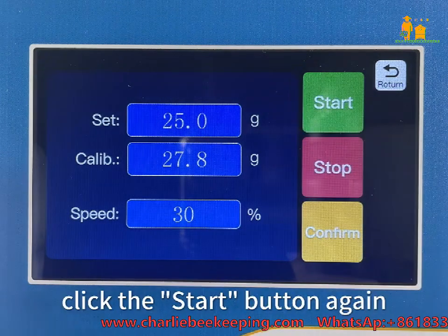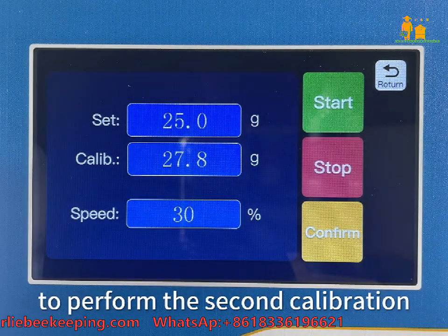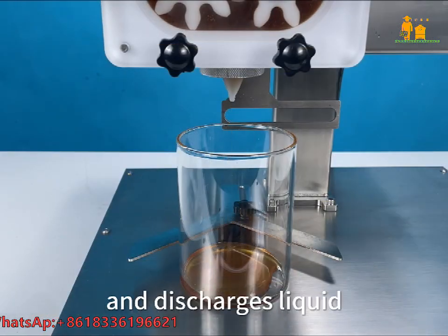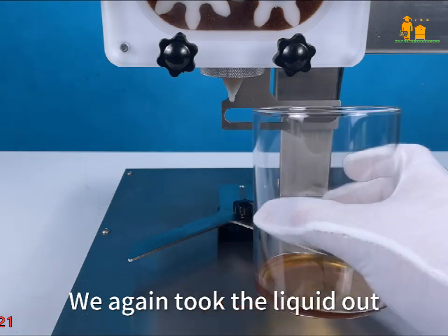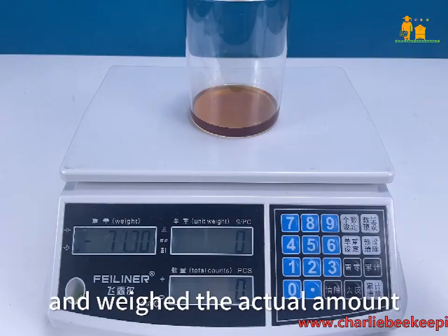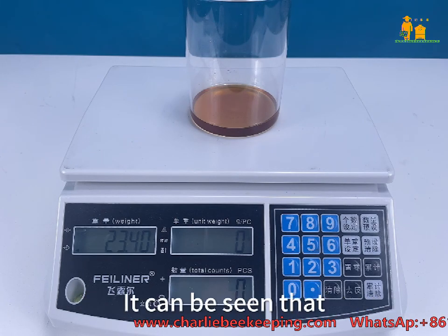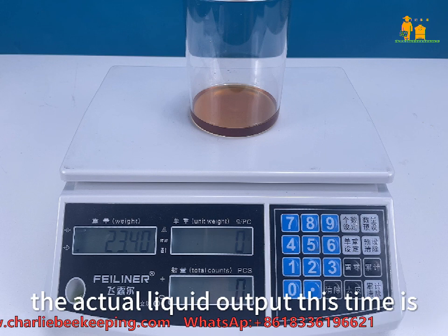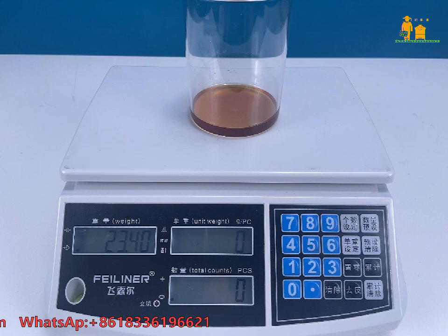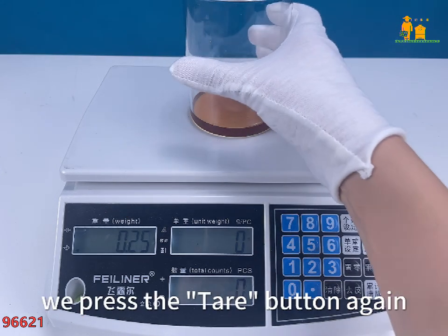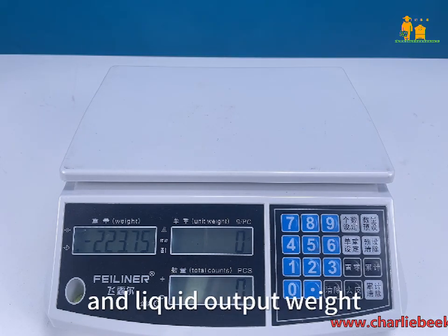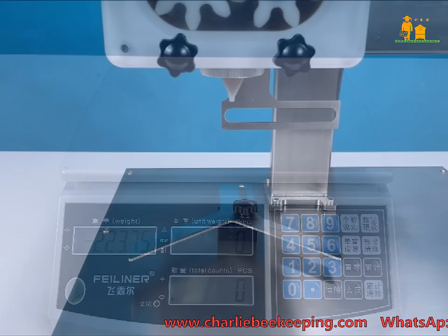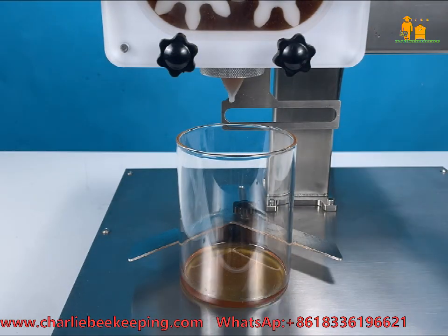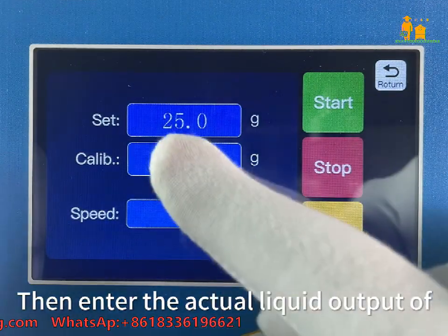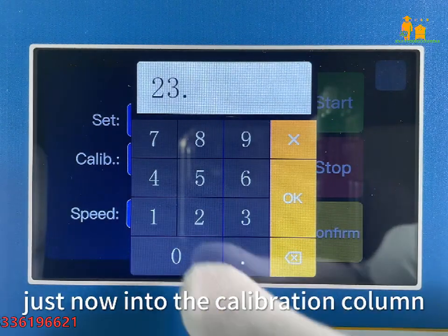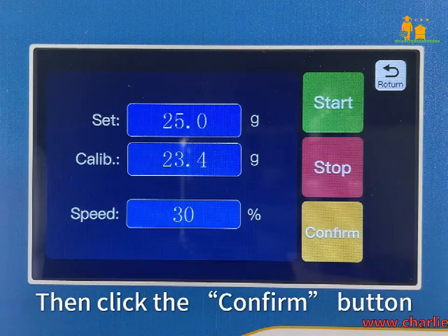At this time, click the Start button again to perform the second calibration. The device starts up again and discharges liquid. We again took the liquid out on an electronic scale and weighed the actual amount of liquid output. It can be seen that the actual liquid output this time is 23.4 gram. At this time, we press the tare button again to remove the bottle and liquid output weight in preparation for the next weighing. We place the bottle again under the outlet. Then enter the actual liquid output of 23.4 gram just now into the calibration column. Then click the Confirm button.